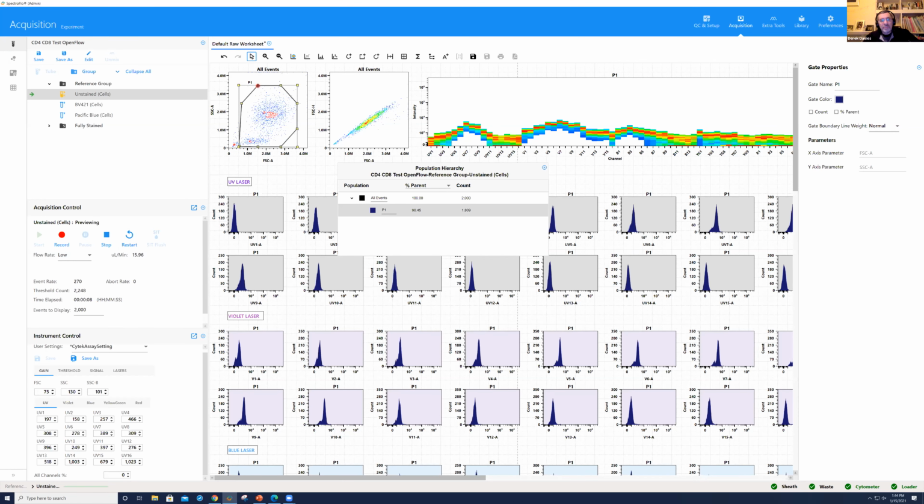Sorry, Kathy, Jim was just asking another question there about do we typically need to change those voltages for most cells because the beads are pushing everything up off scale? So that would be the same for virtually any cell type. Yes, I have never run into a circumstance where I have not had to change that forward scatter gain. Sometimes the side scatter will be close to where it needs to be, but for forward scatter, I would say 100% of the time I've had to reduce it.